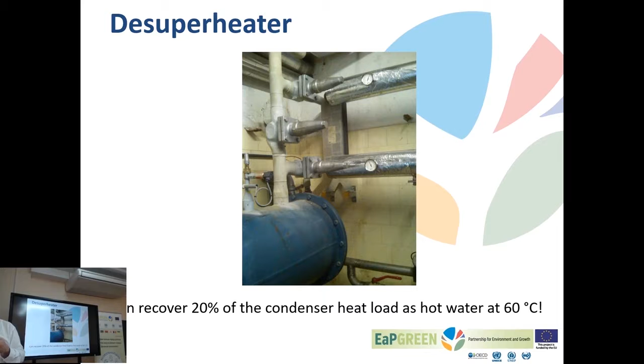About 20% of the heat which else would be dissipated from the condenser, like this, can be recovered as hot water. So actually also the refrigeration cycle can become an effective source of hot water in a very economic way. Because depending on the installation, depending on the size and control we want, this can pay back in a year up to 3 years. So on our terms, this usually is a meaningful investment, especially when designing a new plant, to design for de-superheaters, to support the condenser, to recover heat in a useful way as hot water.